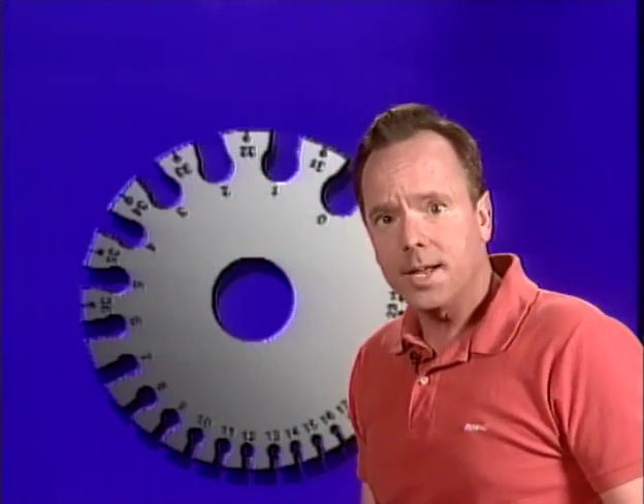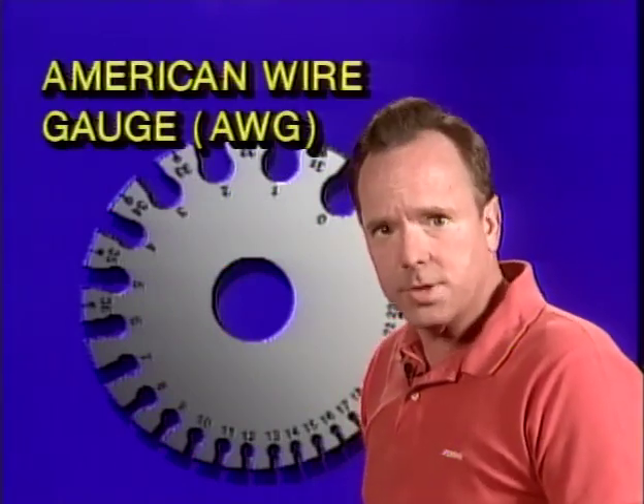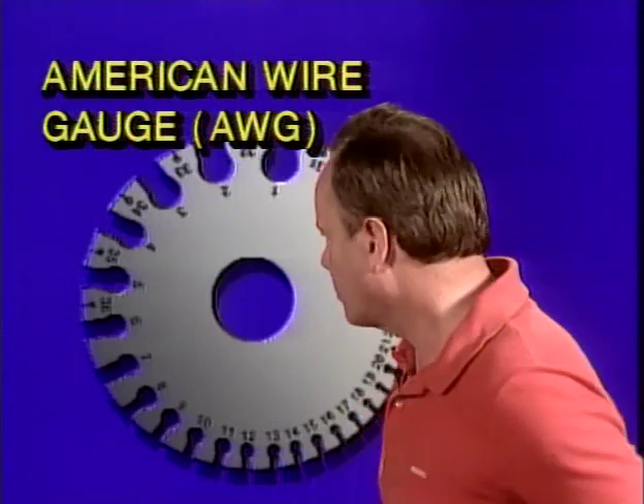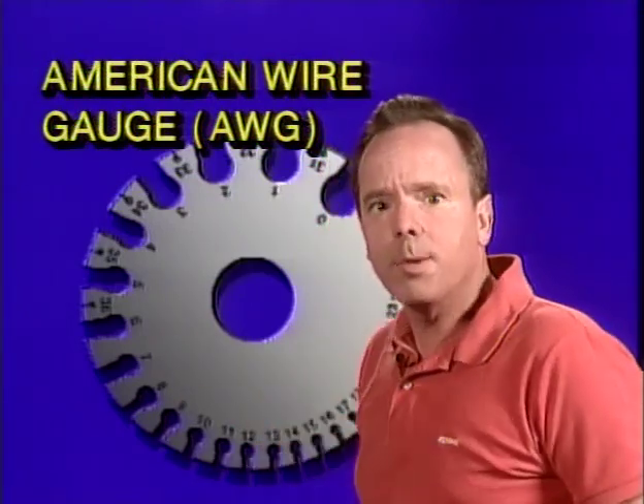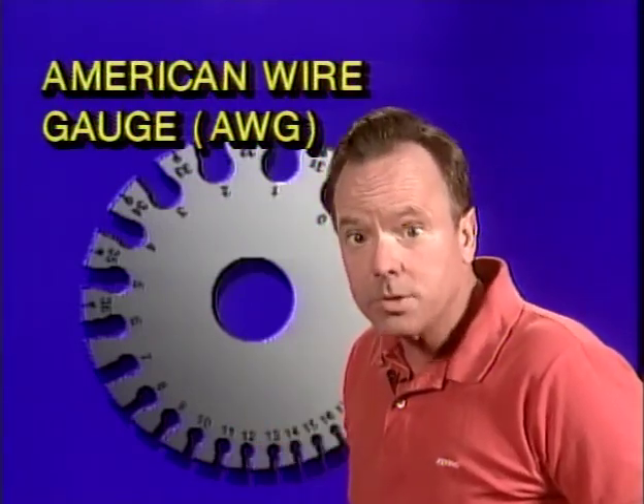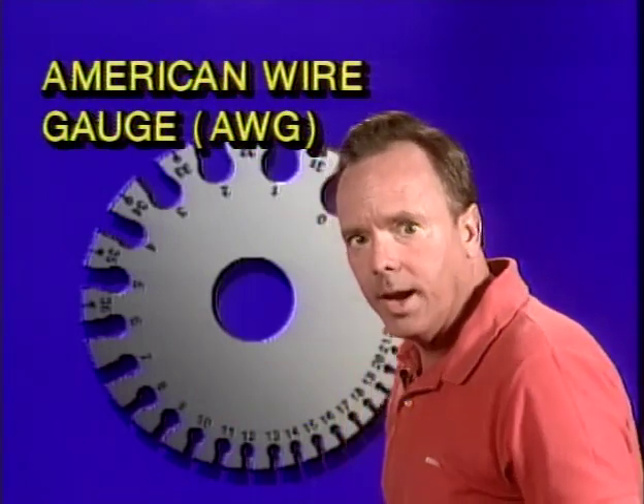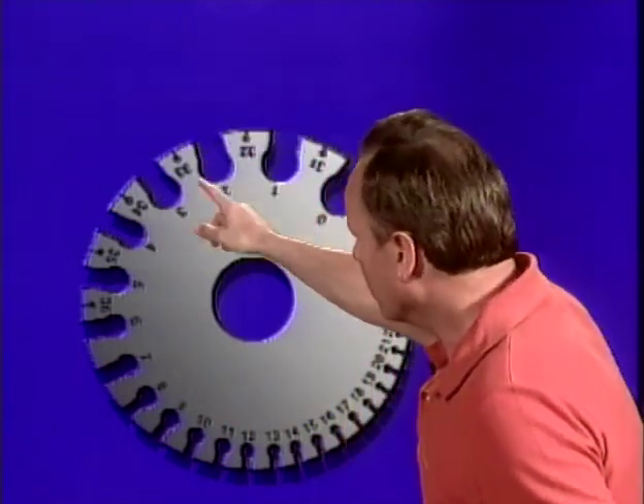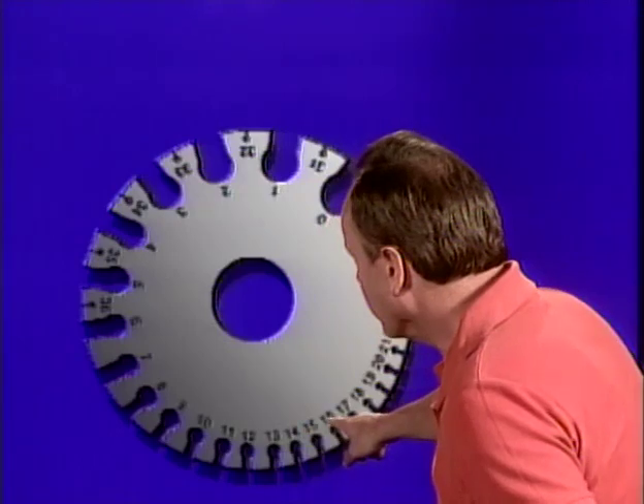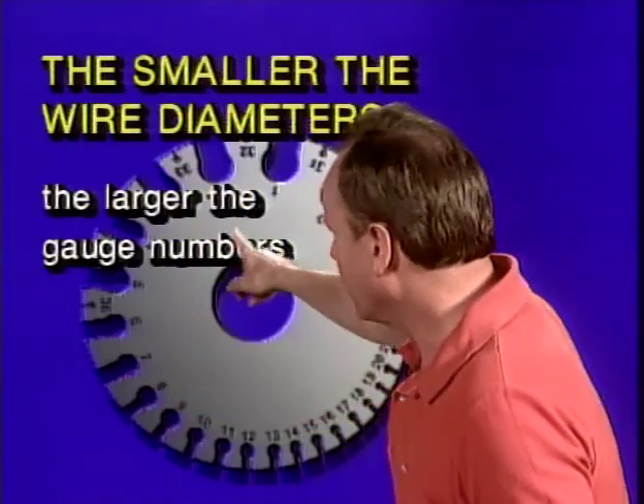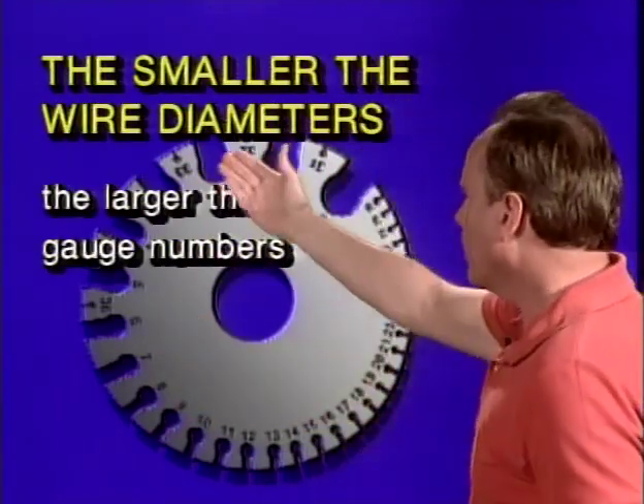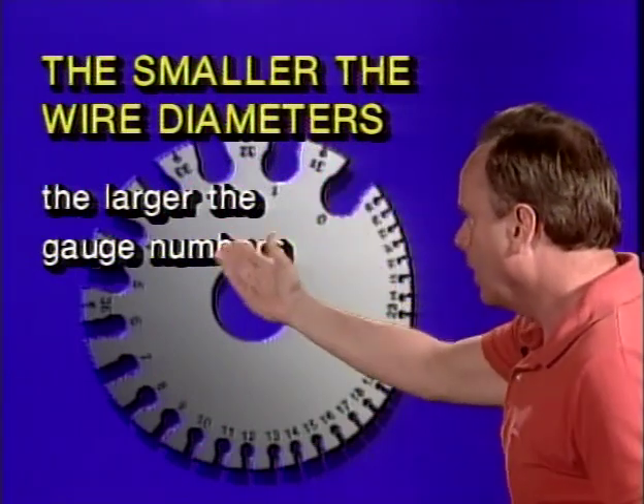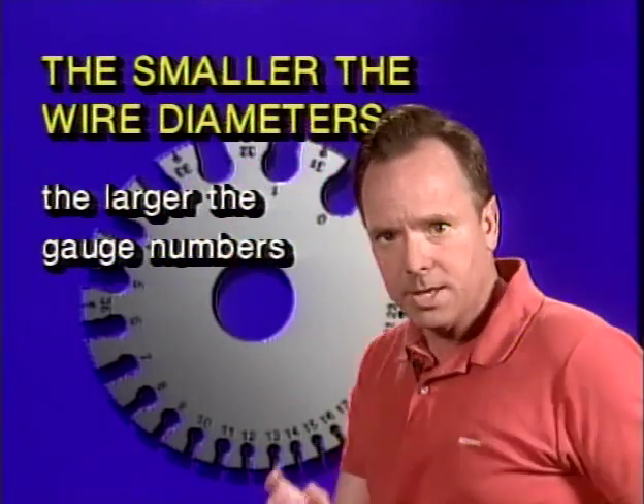In the United States, the American wire gauge system is used to designate electrical wire sizes, and the number assigned to a size is related to its cross-sectional area. Now, the smaller the wire, the bigger the number, and vice versa. And you can see that by looking at this gauge right here. So the smaller the wire diameters, the larger the gauge numbers, and that's one of the things you need to know about this.